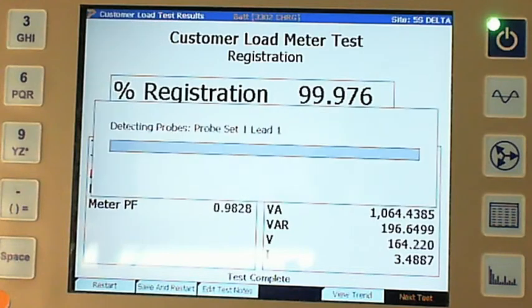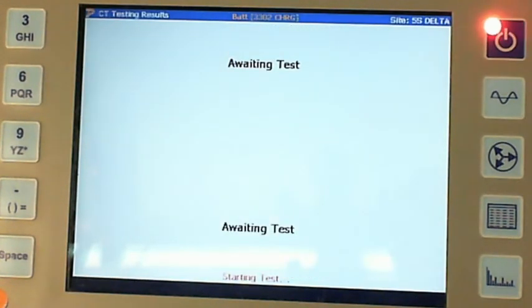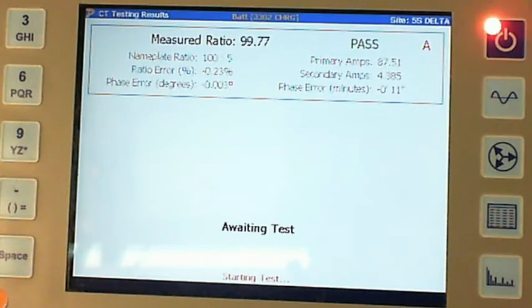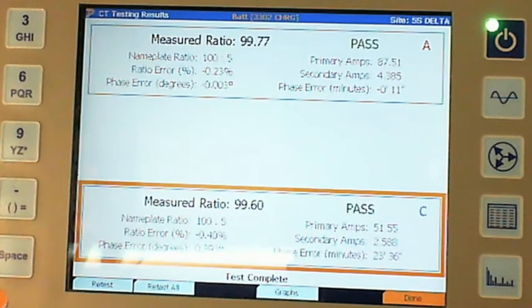Motor load, 208 lighting, yeah. So there's our single line diagram there. And again, I've rigged this up to actually make this work. So I wish you guys could see actually what I've got going on here as far as my CTs. So let's perform the test, CT test here. All right, so now remember we're summing the primary amps and summing the secondary amps. And so, of course, on C phase, that's the 208 wild lag. So we've got 51 amps primary and two amps on the secondary side. So that's pretty much passed there.